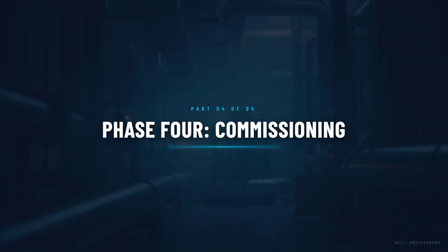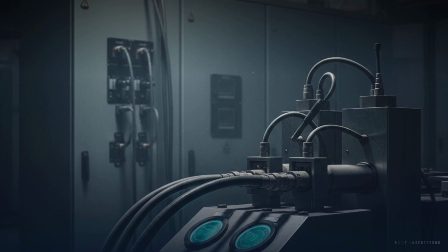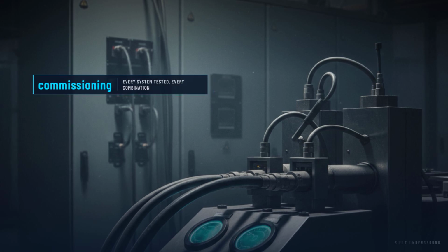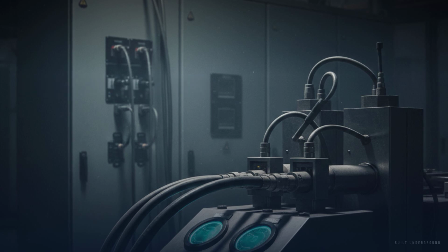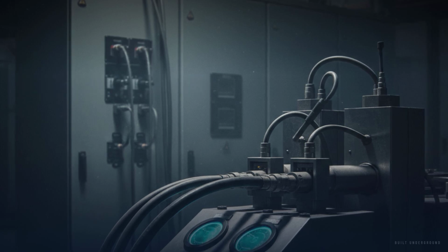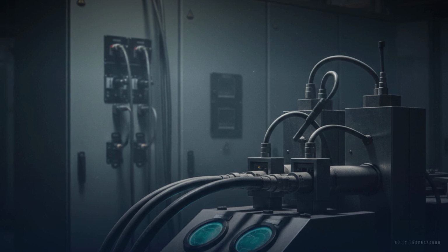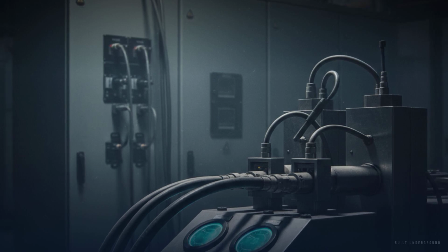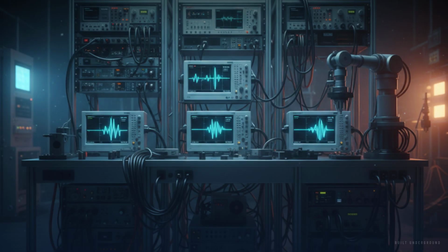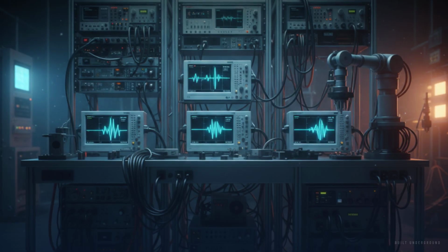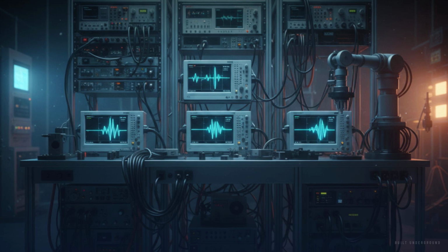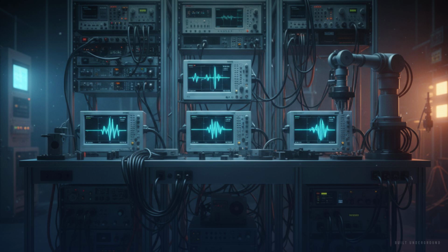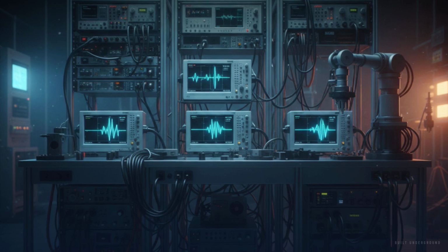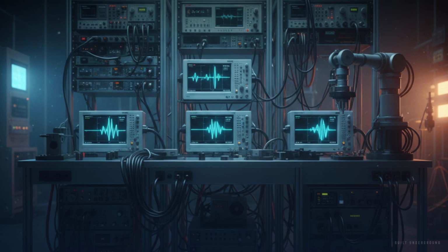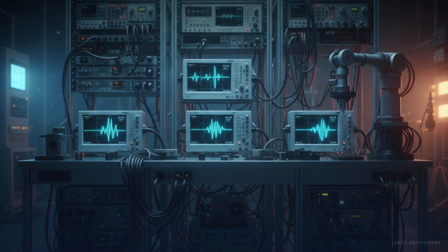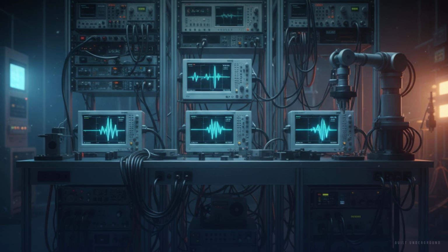This is the phase that separates a building from a working data center. Commissioning is the systematic process of testing every single system individually and together to prove it works as designed before a single server gets installed. Power systems get tested under full load. Generators are started and run for hours. UPS systems are deliberately switched to battery to verify the transfer is seamless. Cooling systems are tested to prove they can handle the designed heat load.